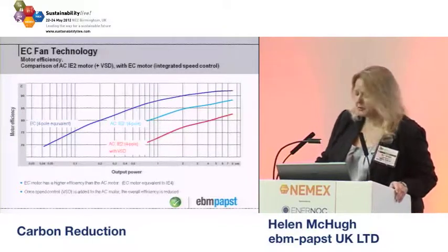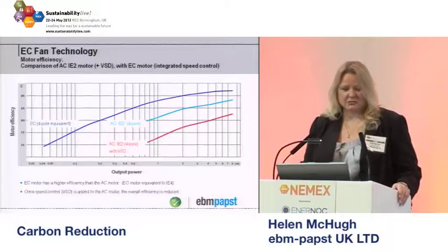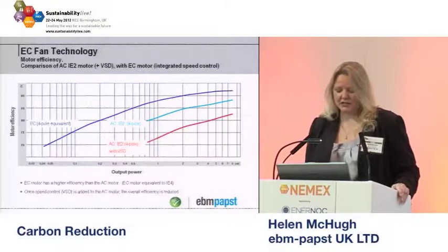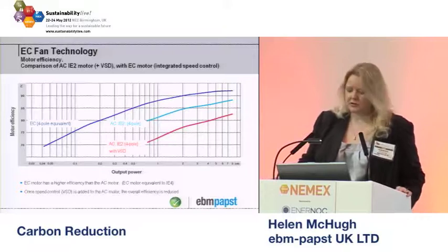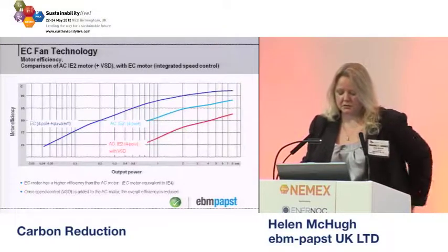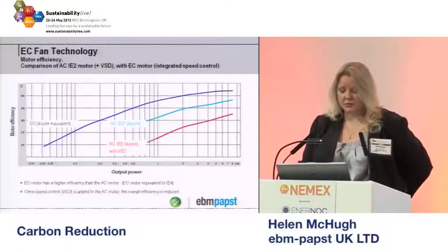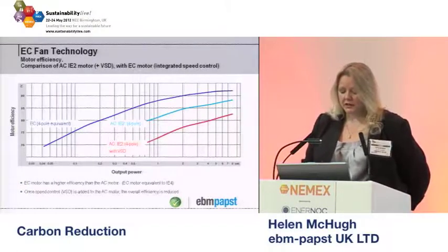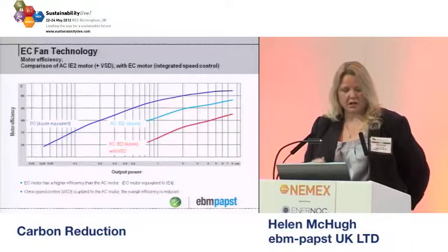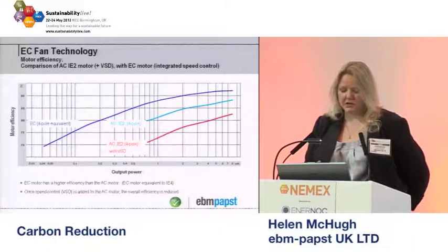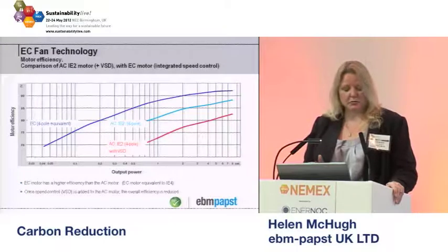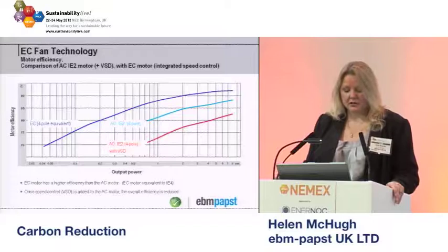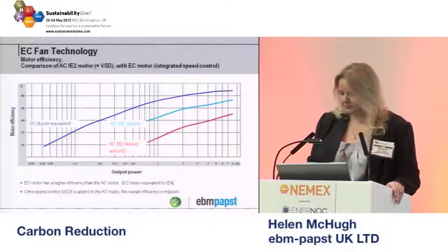You can look at this later because I'm sure you get the presentation, but that's comparing energy efficiencies. So the centre line there is looking at the energy efficiency of a typical AC motor. So you've got the efficiency up the side and the size of the motor along the bottom. You add a variable speed drive, which you typically do, and you have the red line. We're comparing the top line. So for a 1 kilowatt motor, we're comparing an efficiency for normal AC of sort of 72%, and we're looking at something well over 80%.